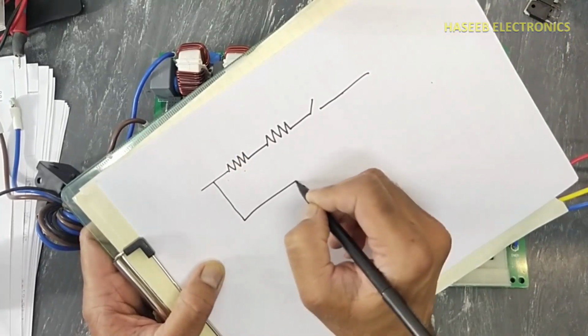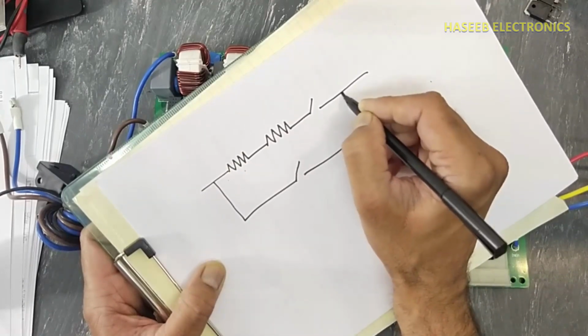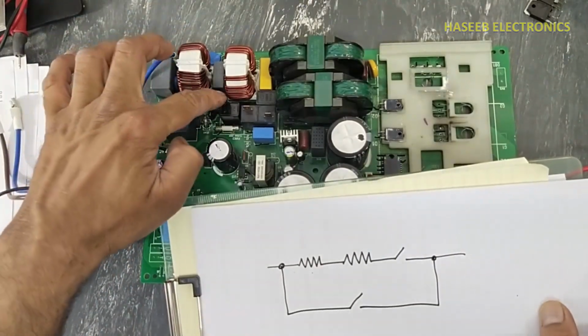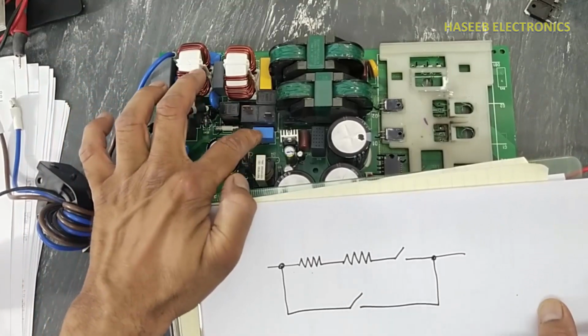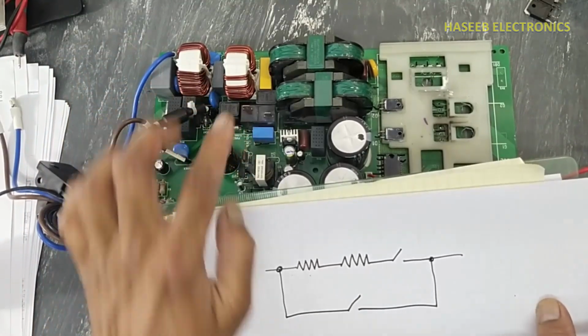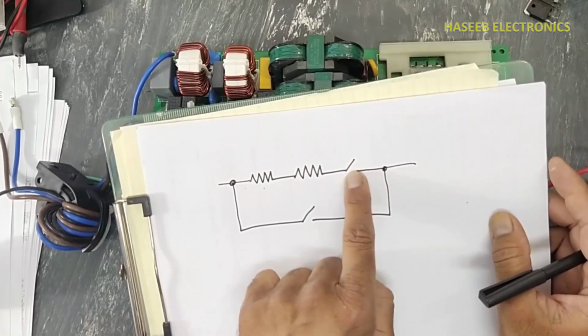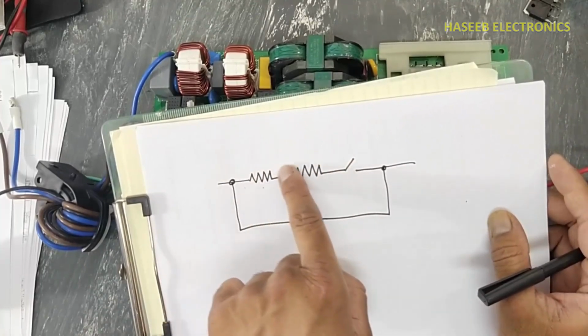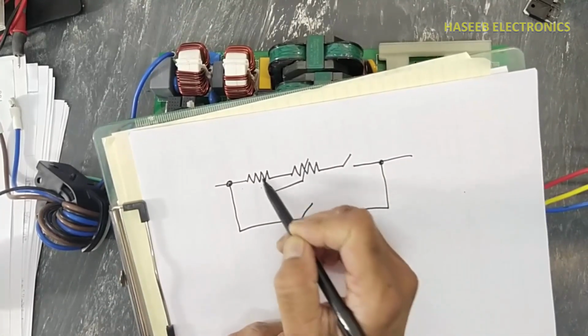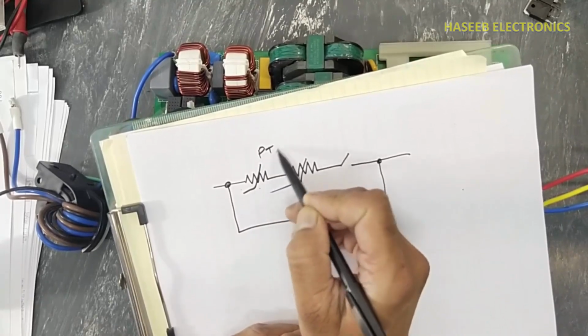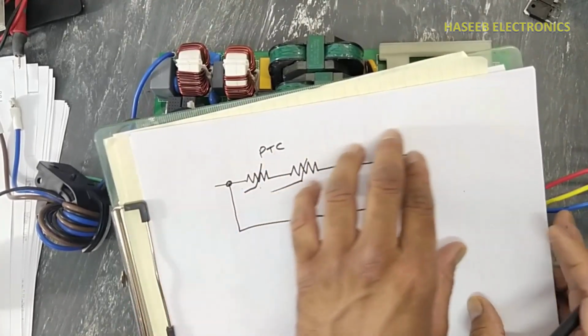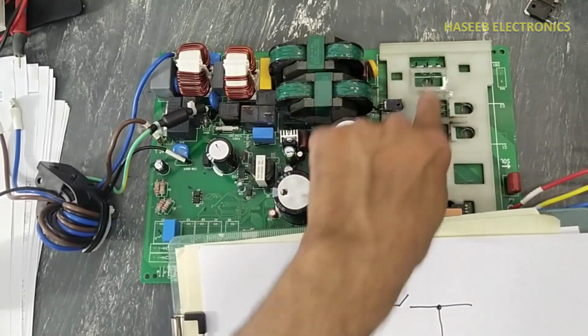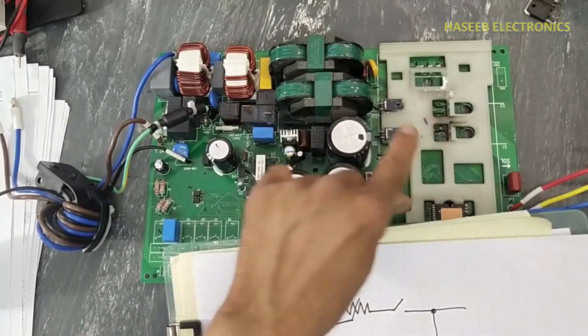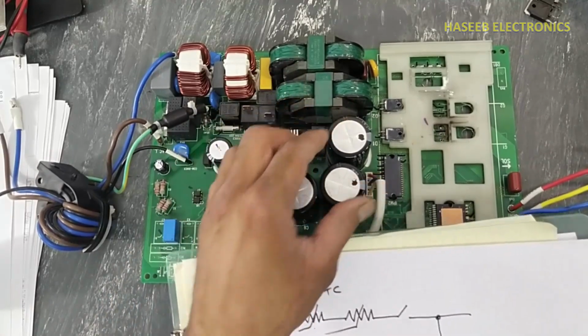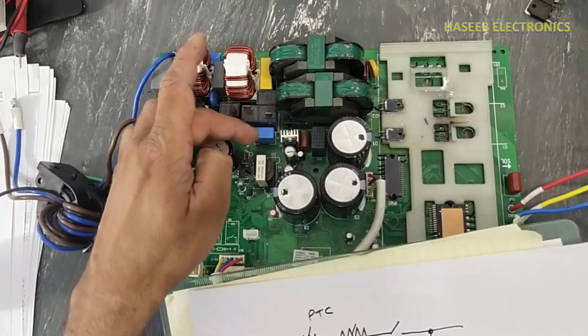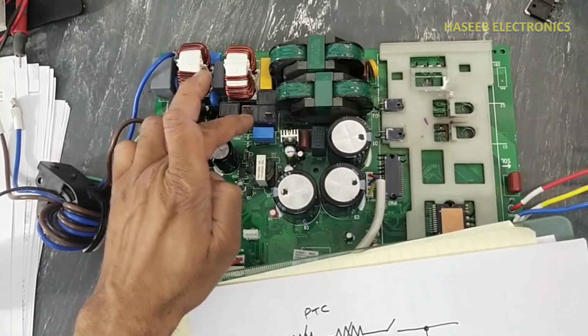And then we have the bypass relay. When we apply power, the voltage will reach the contacts of this relay. When this relay turns on, it will allow current to flow through these PTCs. Then the voltage will reach the bridge rectifier and be provided to the booster section. When the voltage is maintained, the microcontroller will turn on this bypass relay.